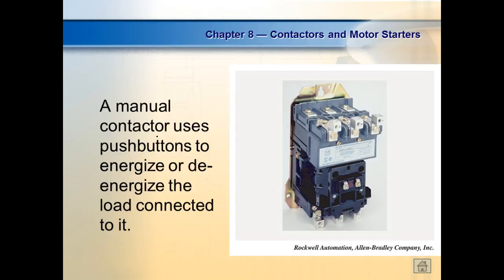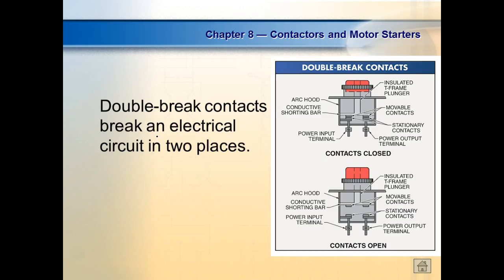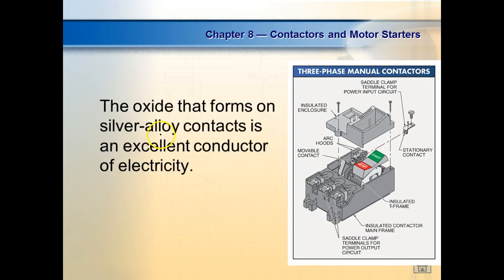So newer contactors, newer motor starters will probably be solid state. Older installations will probably be heaters because they're a lot cheaper. And they're cheaper to maintain too. Talked about double break contacts, right? Everybody understand what's the advantage of double break contacts? They have a better tendency of breaking. They don't weld together here as much.